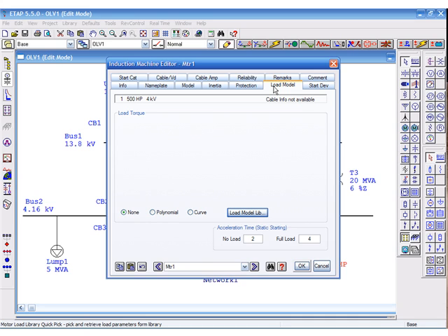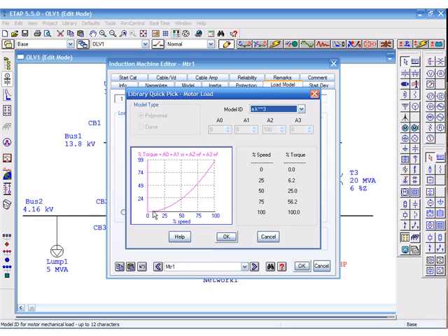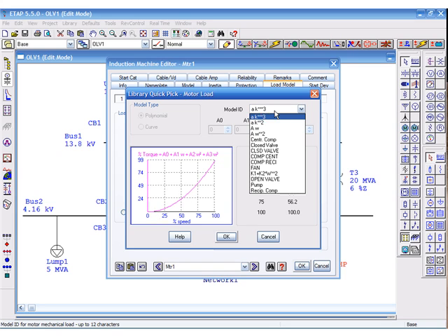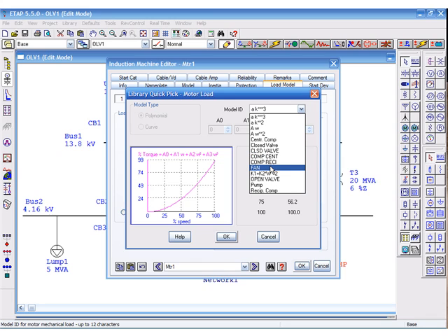Next, we'll go to the load model page, where you'll be specifying the driven or the connected load. The connected load can be specified as a polynomial equation, which is a function of speed and torque. The plot shows you the representation of that equation.